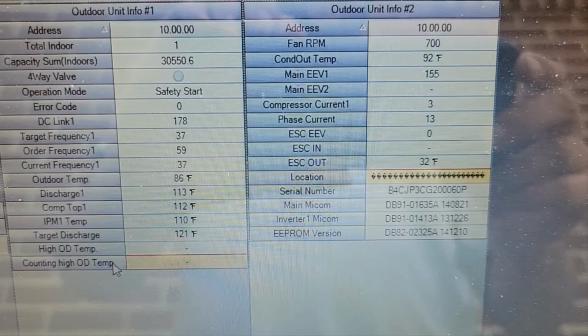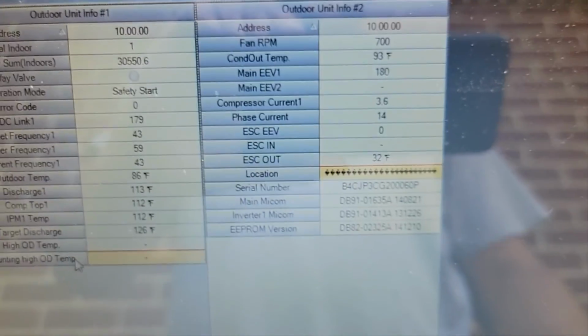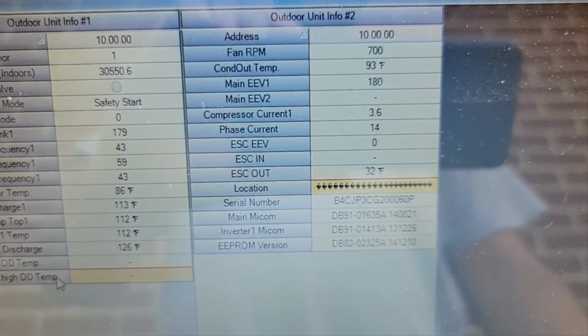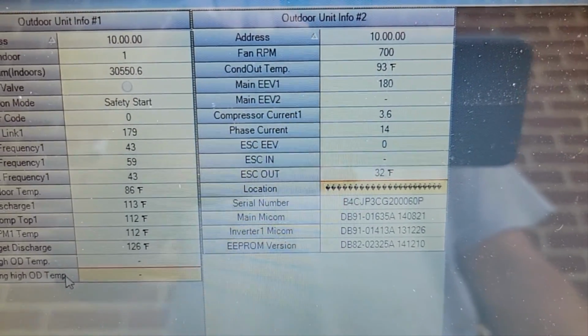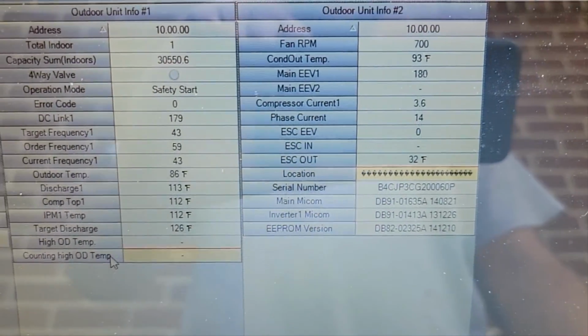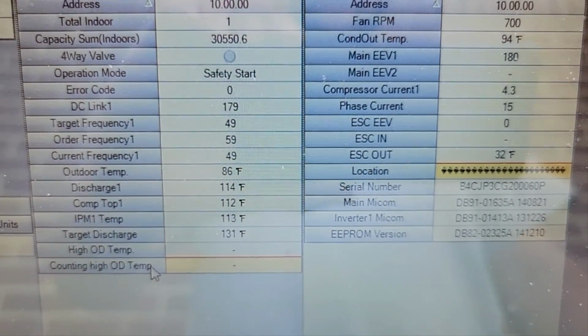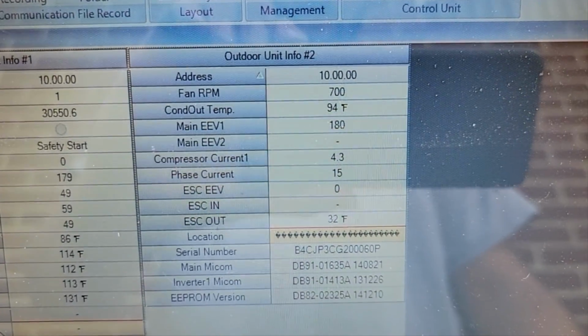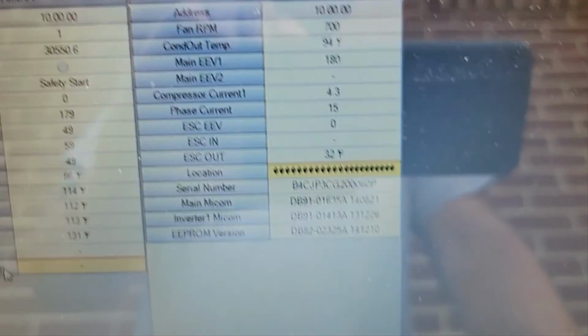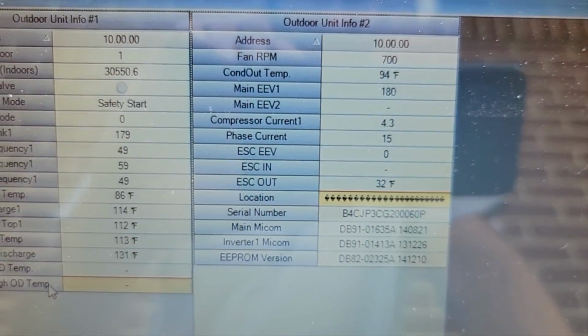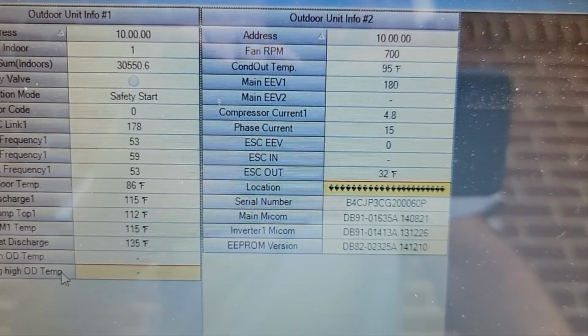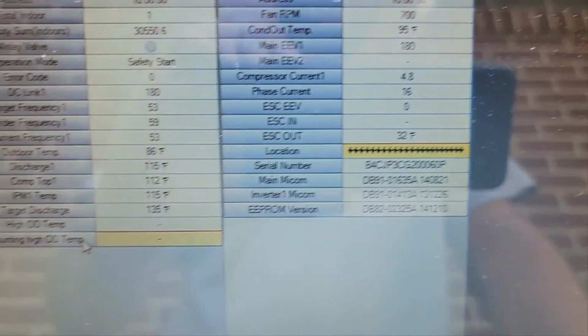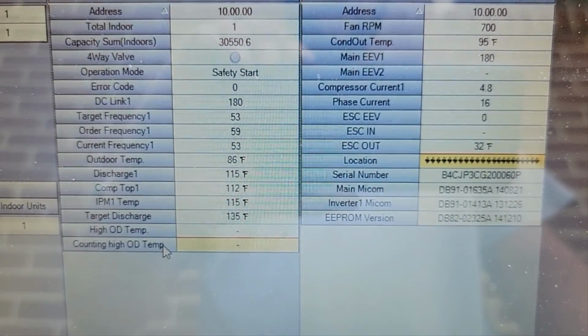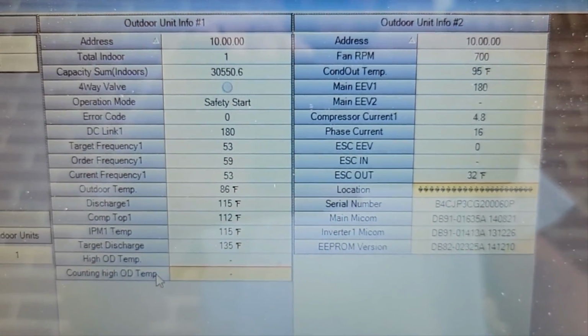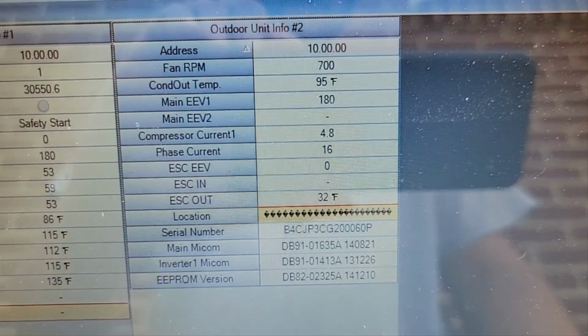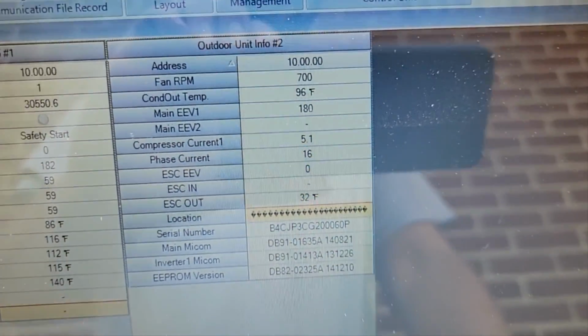Should see a little bit of a change. It's only literally been 30 seconds since I hit the stop button on the camera. EEV just changed from 155 to 180. Ramping up some more. Target discharge 135. Oh yeah, I hear it ramping up now.